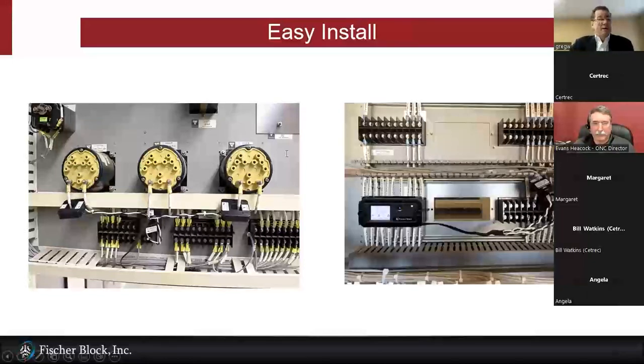We commonly get asked how do we specifically pick up volts and current without any wiring. Here's an example: on the left is the back of a panel. When we install our device, which we call a smart block, on the front of the panel, we typically use a hollowed out bolt, what we call a smart bolt, that we mount on the panel underneath our device. We then run an insulated tube right to the back of the panel and snap on a three-phase split core CT probe assembly. Those are hinged - not shown in the picture - but they hinge open and just snap around the secondary wiring, so there's no new wiring and no disruption to the existing wiring as we make that connection.